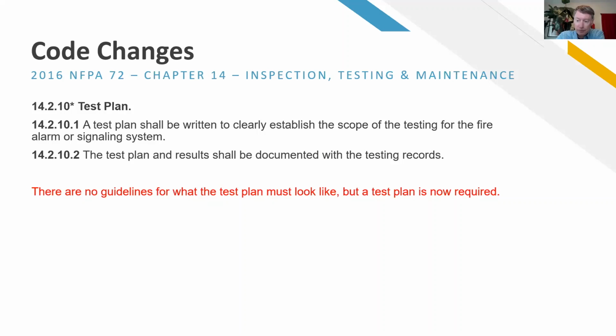Mark, anything? Yeah, if you have a building with unique circumstances or any special application, we've seen before that sometimes it's hard to get in and test devices because you have a 24/7 operation, like a factory assembly line. In your test plan, that would be a good place to say, hey, we can only test this part of the system on Christmas Day because that's when they shut the line down. No one would want to do that, but sometimes we end up in those situations.